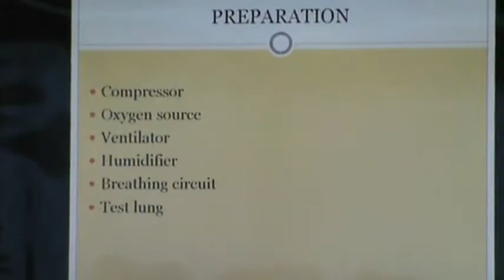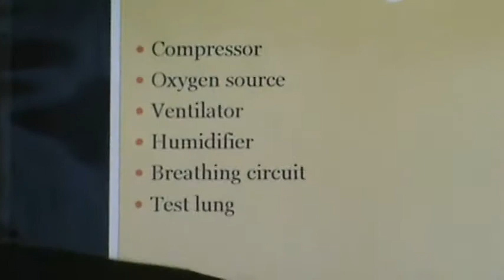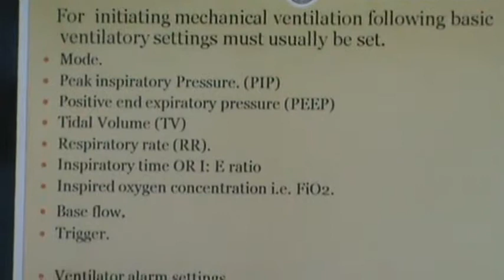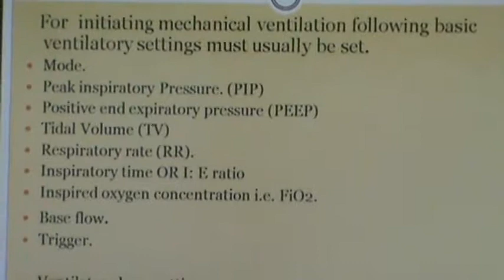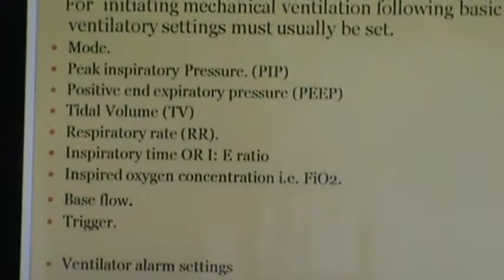This is the basic preparation. Before initiating ventilator, we have to keep ready compressor, oxygen source, ventilator, humidifier, breathing circuit, and test lung. Initial ventilation settings: we have to set the mode of ventilation, then PIP, PEEP, tidal volume, respiratory rate, I time. By that we are setting the I:E ratio, FiO2, base flow, trigger, and ventilator alarm settings.